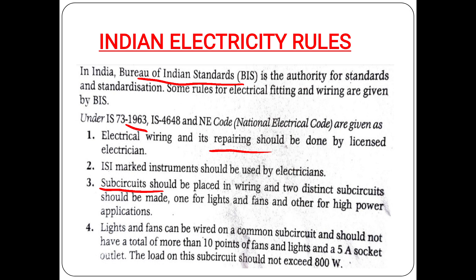One sub-circuit for lights and fans, and another for high power applications. A common sub-circuit wired for lights and fans should not have a total of more than 10 points. It should include a 5-A socket outlet, and the load on this sub-circuit should not exceed 800W.